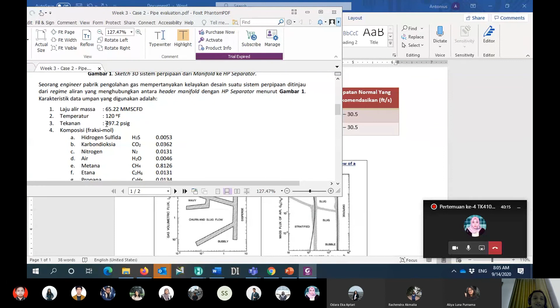So let's make this definition, because our pressure is quite high. In the preceding problem definition, our pressure is around 35 bar, so it's higher than 6 bar. So we will use this definition, which is around 0.23 to 0.34 bar per 100 meters.